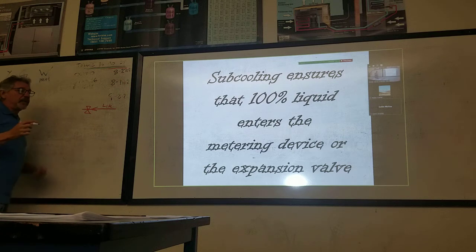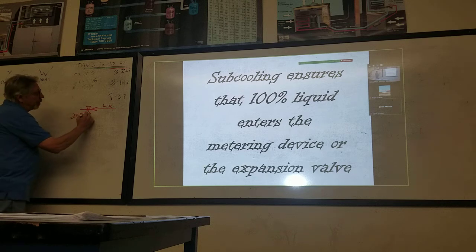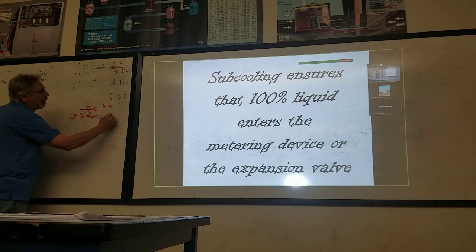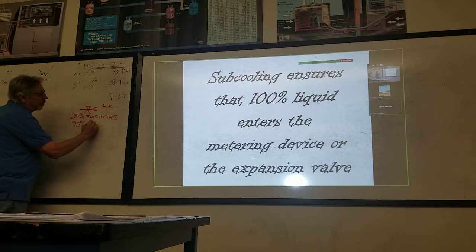Technically, what happens with that refrigerant after it leaves the metering device is about 25% vapor, which is called flash gas, and 75% liquid.